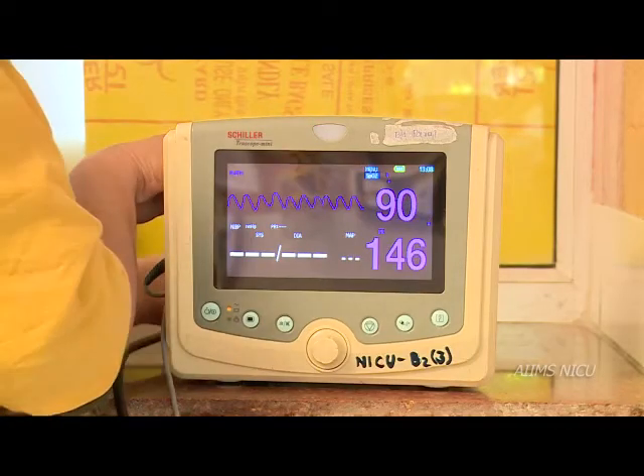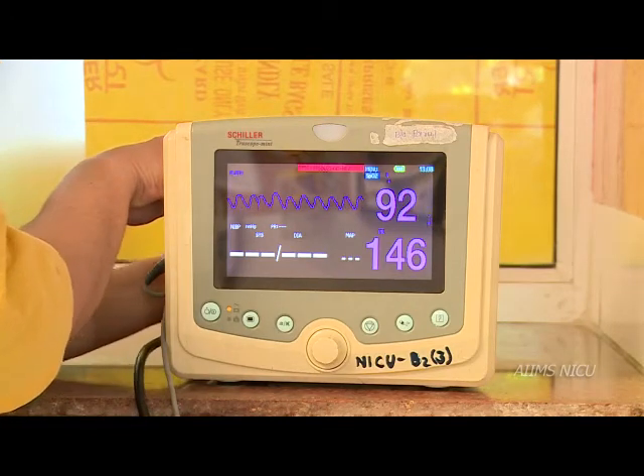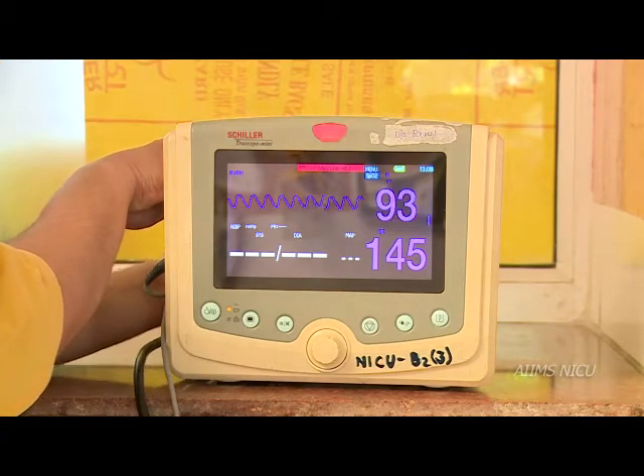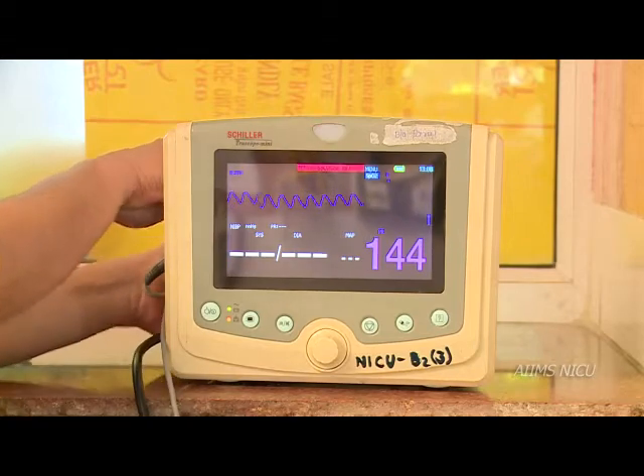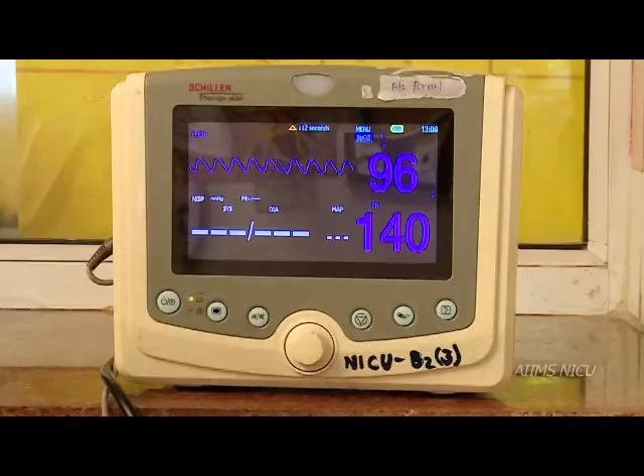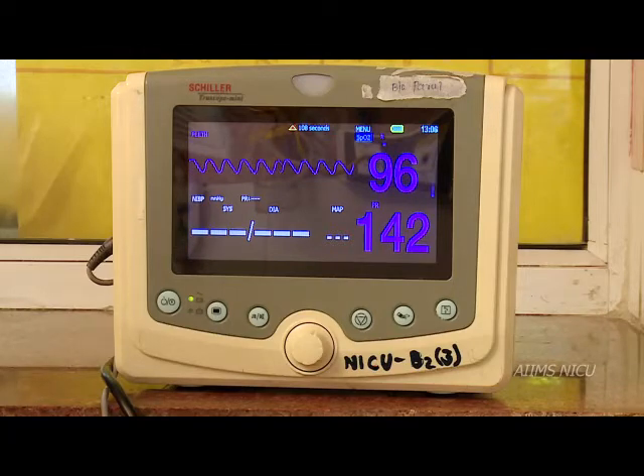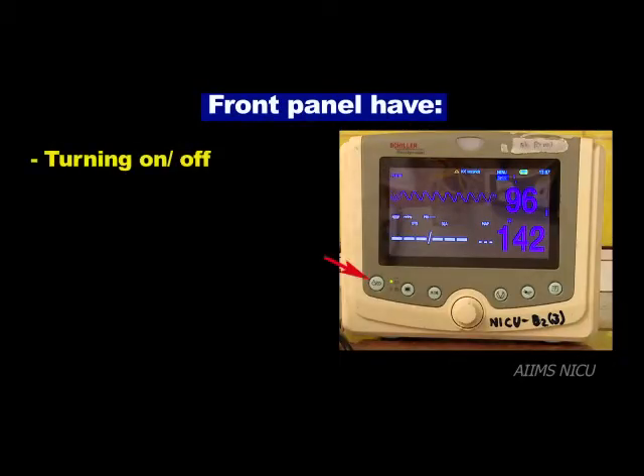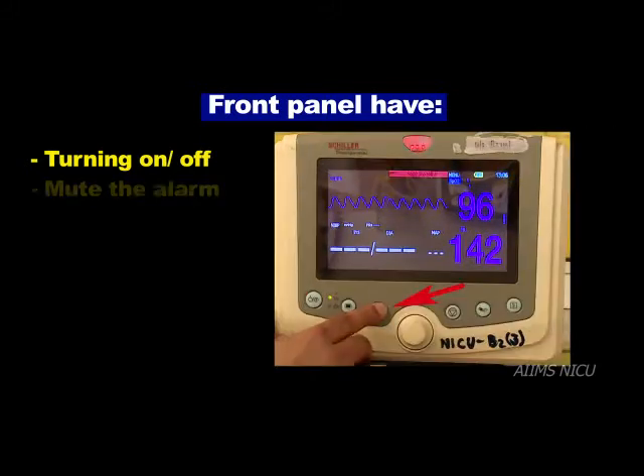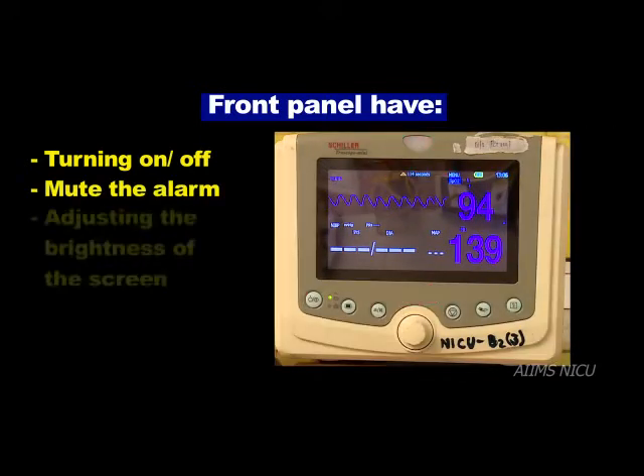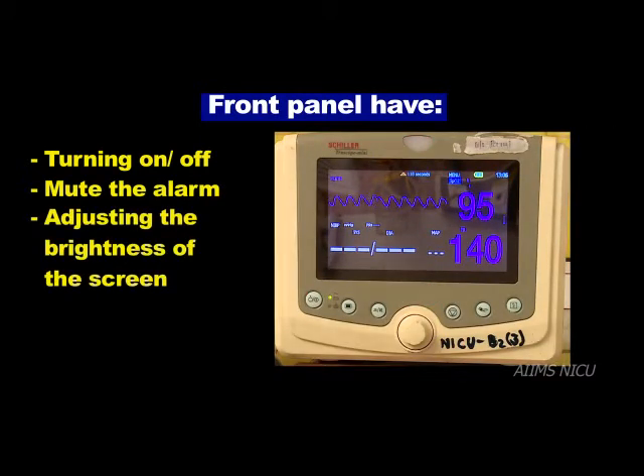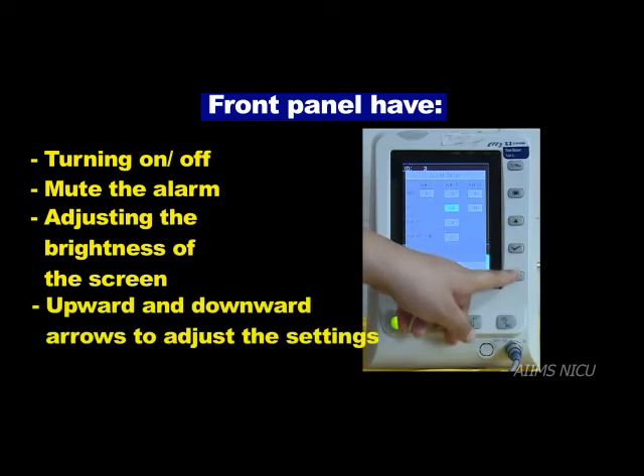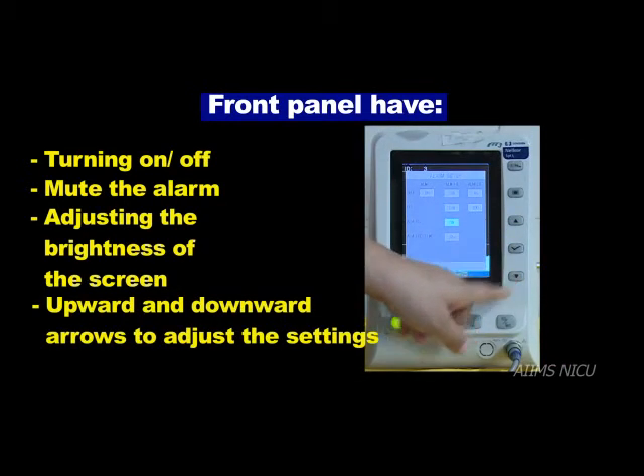Pulse oximeters have to be connected to AC power connection through the power cord provided. If the battery is fully charged, it can be used without AC power, especially during transport of babies. The front panel of the pulse oximeter contains the knobs or buttons for turning on or off the pulse oximeter, mute the alarm, adjusting the brightness of the screen, upward and downward arrows to adjust the settings, indicators of battery status, AC adapter connections.